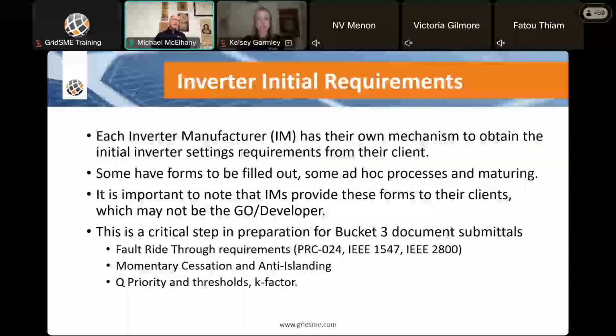So into the next one, each inverter manufacturer has their own mechanism to obtain initial inverter setting requirements from their client. And this is one of the themes that you'll hear throughout this part of the presentation: attachment A is attachment A, no matter who the inverter manufacturer is. But the inverter settings reports and the settings themselves within inverters are wildly different from inverter manufacturer to inverter manufacturer, and sometimes even from Gen 2 to Gen 3 to Gen 4 inverters, how it does something and how you set it up to do that thing is different.